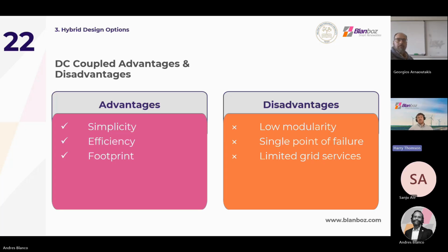Now looking at the disadvantages, the DC coupled solution does offer low modularity. The battery, PV, and the inverter are tightly integrated, and it reduces the ability to independently optimize power, energy, C-rate, and duration of the BESS. This is because the packages usually come integrated, and it limits the procurement options available. Additionally, there's typically a single point of failure. In an event where the PCS fails, both the PV and BESS cannot deliver to the grid due to the setup, increasing downtime and lost revenue. And finally, it limits the grid services that the BESS can deliver.